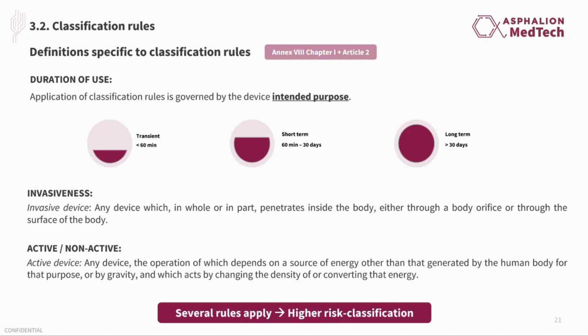We also have active devices that rely on an external energy source other than that generated by the human body. Important, and this is quite important, because if several rules, or if within the same rule several sub-rules, apply to the same device based on the device's intended purpose, the strictest rule and sub-rule resulting in the higher classification shall apply.